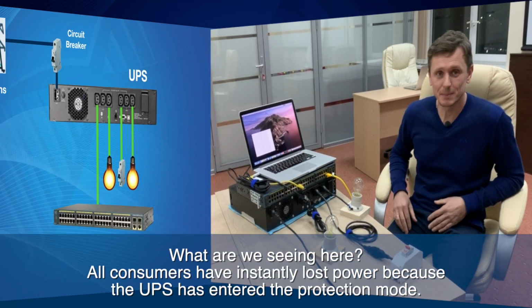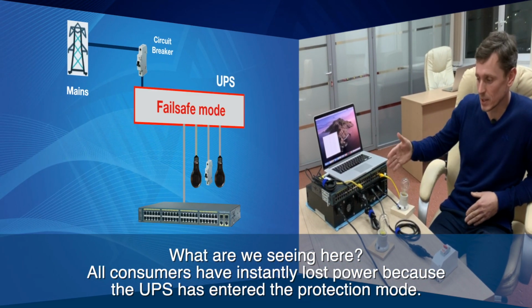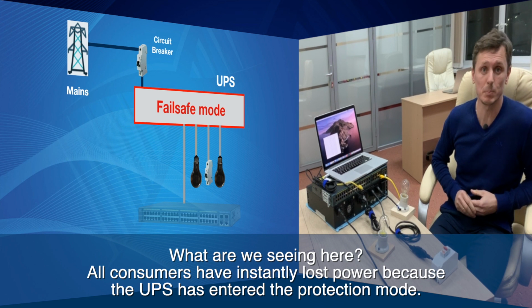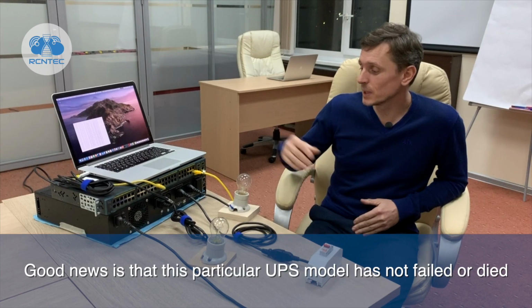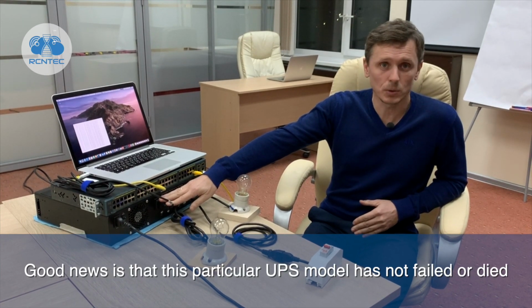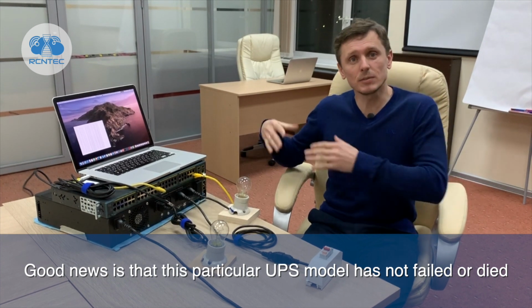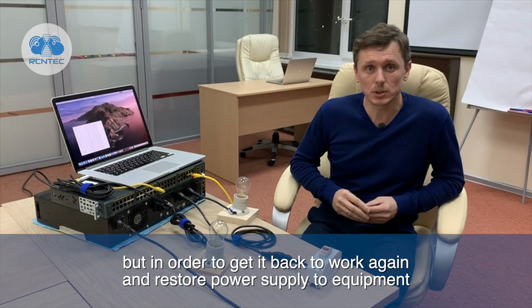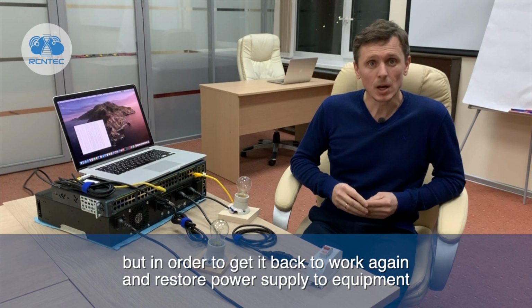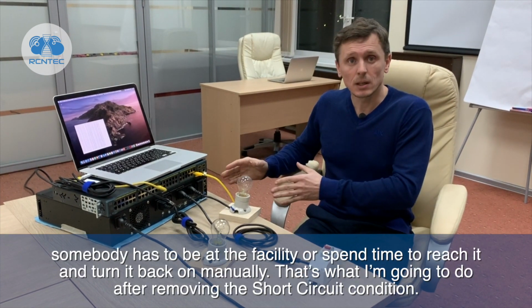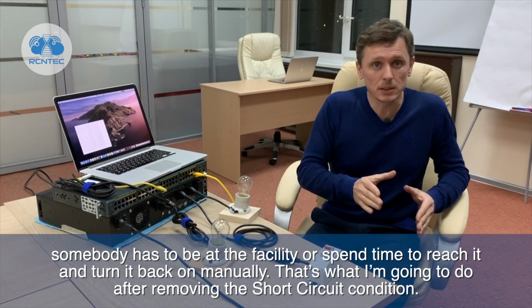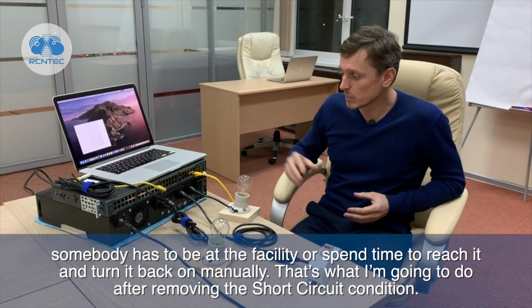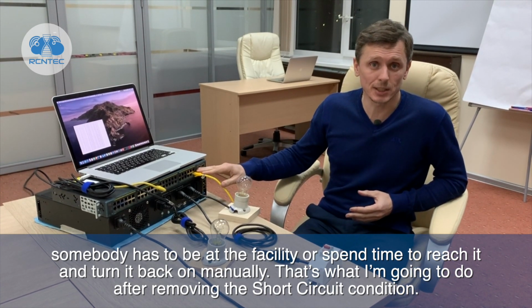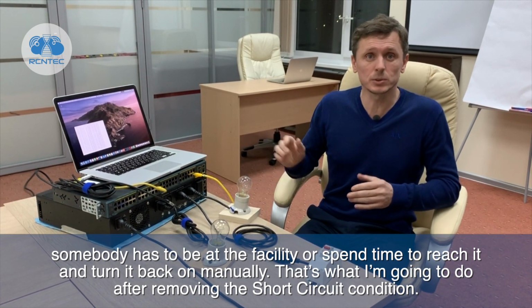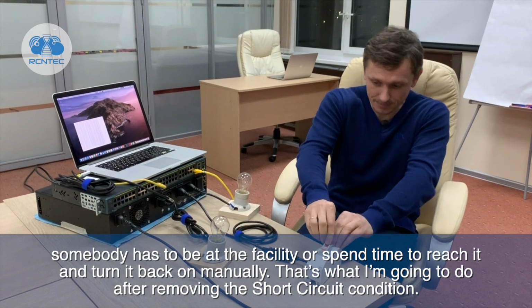What are we seeing here? All consumers have instantly lost power because the UPS has entered the protection mode. Good news is that this particular UPS model has not failed or died, but in order to get it back to work again and restore power supply to equipment, somebody has to be at the facility or spend time to reach it and turn it back on manually. That's what I'm going to do after removing the short circuit condition.